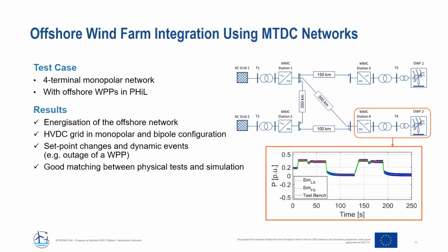And using this setup, we could show that, for example, during set point changes, but also during dynamic events, such as an outage of a wind power plant, there's a good matching between the physical tests and simulations. So you can see this here in the graph, for example, for the power flow of the offshore wind turbine. On the one hand, using the physical test bench converter in power hardware in the loop.